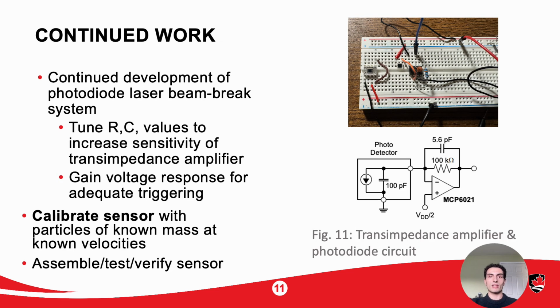Next steps will include developing the photodiode laser beam break circuit and tuning the transimpedance amplifier for an adequate response of the photodiode. Once this is complete, it will then be interfaced with the piezoelectric sensor to determine the velocity of the particle. Lastly, the sensor will be calibrated with particles of known mass and velocity before it can then be fully tested and verified.